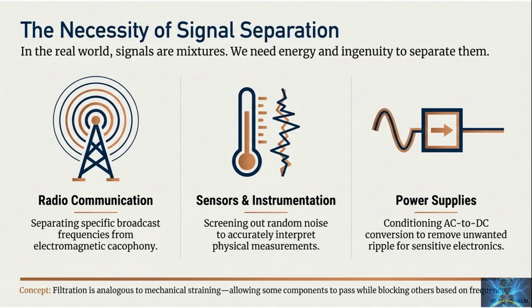The core problem: real signals are messy. In textbooks, signals are clean. In the real world, signals ride on top of electrical noise, interference, ripple, vibration, and switching transients. A flow transmitter might be stable, but the wiring may pick up noise. A pressure signal might be real, but the process may be chattering. A power supply may be mostly steady, but it has ripple. Filters are how we keep the measurement useful by suppressing what does not represent the process.